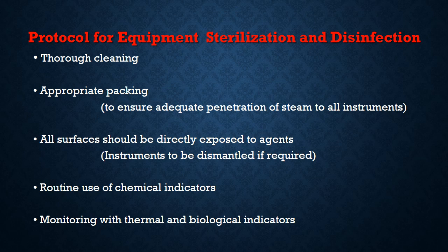Instruments in laparoscopic surgery may need to have their external sheaths removed so that all surfaces are exposed to the steam. And chemical indicators must be used routinely so that you know that the steam has reached all parts of the pack, and thermal and biological indicators are also used to ensure adequate sterilization.